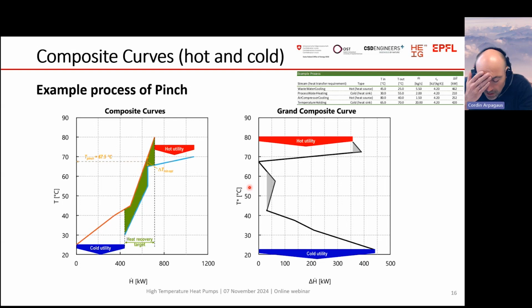Then we go to energy analysis. Here is an example of a pinch analysis. We look at streams that need to be heated up and cooled down in an industrial site, and we make composite curves of these hot and cold streams. By pinch analysis, you can find out how much heat can be recovered between the streams, and what hot utility and cold utility needs are necessary.